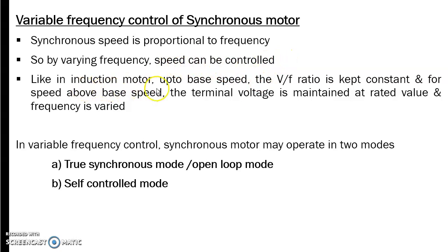So like in induction motor, up to base speed, V by F ratio is kept constant. For speed above base speed, the terminal voltage is maintained at a rated value and frequency is varied. Hence the maximum torque will be naturally reduced. So in variable frequency control, synchronous motor may operate in two modes. These things you should never ever forget. There are two modes of operation of variable frequency control of synchronous motor.